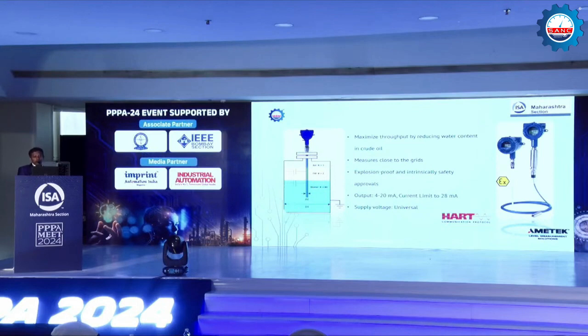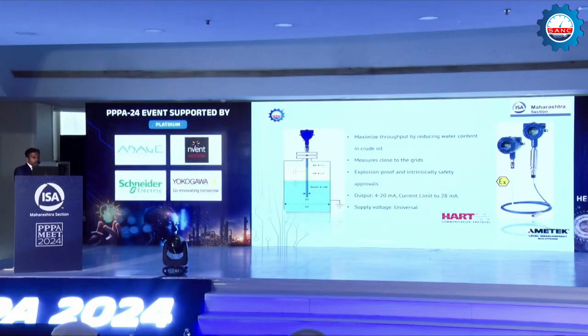Then again, we pour the water, and we get some picofarad value. Let's say we get 800 picofarad, and that becomes the span level. So whenever there is oil, there will not be any measurement. It shows 0. But the moment water enters, it starts reading, because we made oil 0. So that's how it measures the interface level accurately.